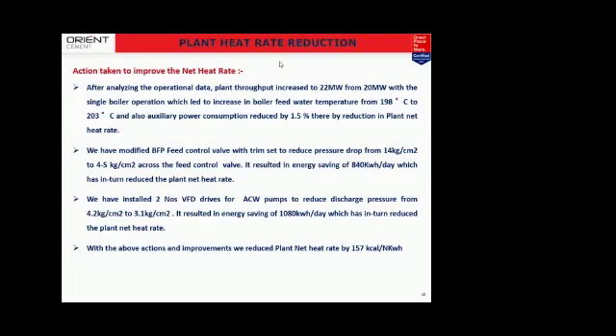And next, one more modification, which is a very interesting modification. Right from the beginning, we are operating a boiler feed control valve. We saw a pressure drop of 14 kgs across the feed control valve, that is the FCV. From the boiler feed pump, it comes to the feed control valve, and after the feed control valve, we were observing a 14 kgs drop in the pressure. So we consulted the control valve vendor and installed a new trim set inside the boiler feed control valve. After installing that trim set, we brought down the 14 kgs per centimeter square drop to 4 to 5 kgs per centimeter square drop, which also resulted in an energy saving of 840 kilowatt hour per day. So this was a major saving which we could get.